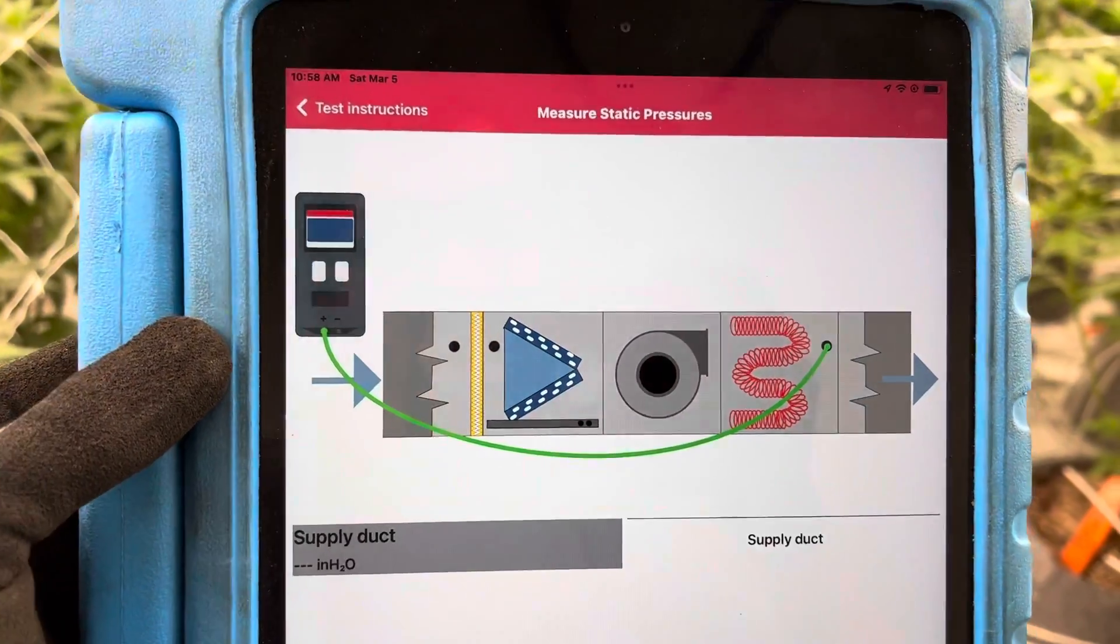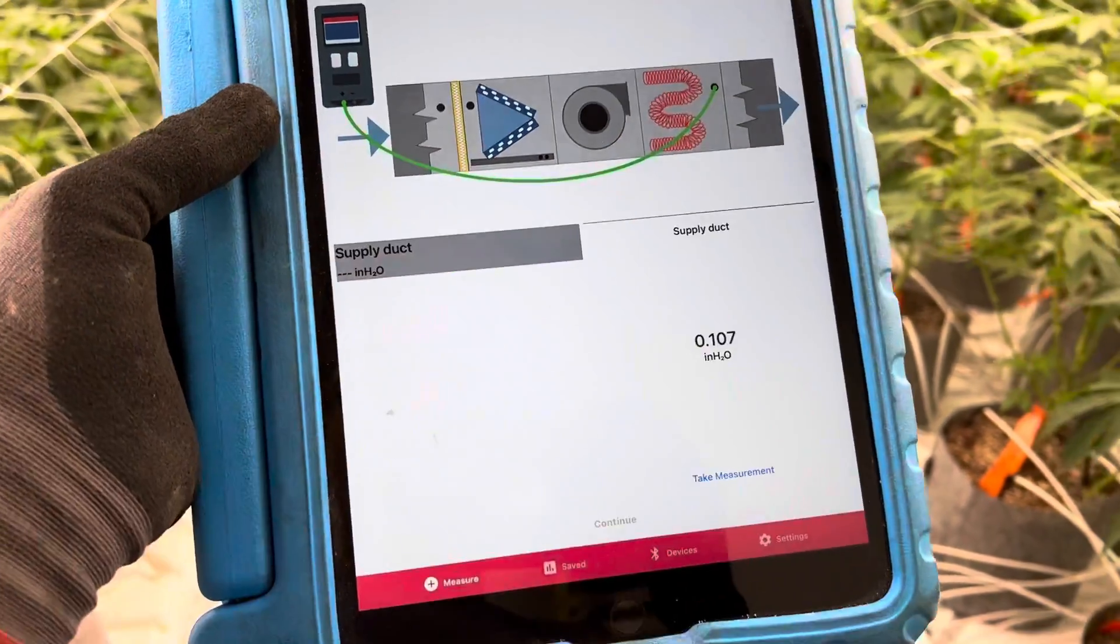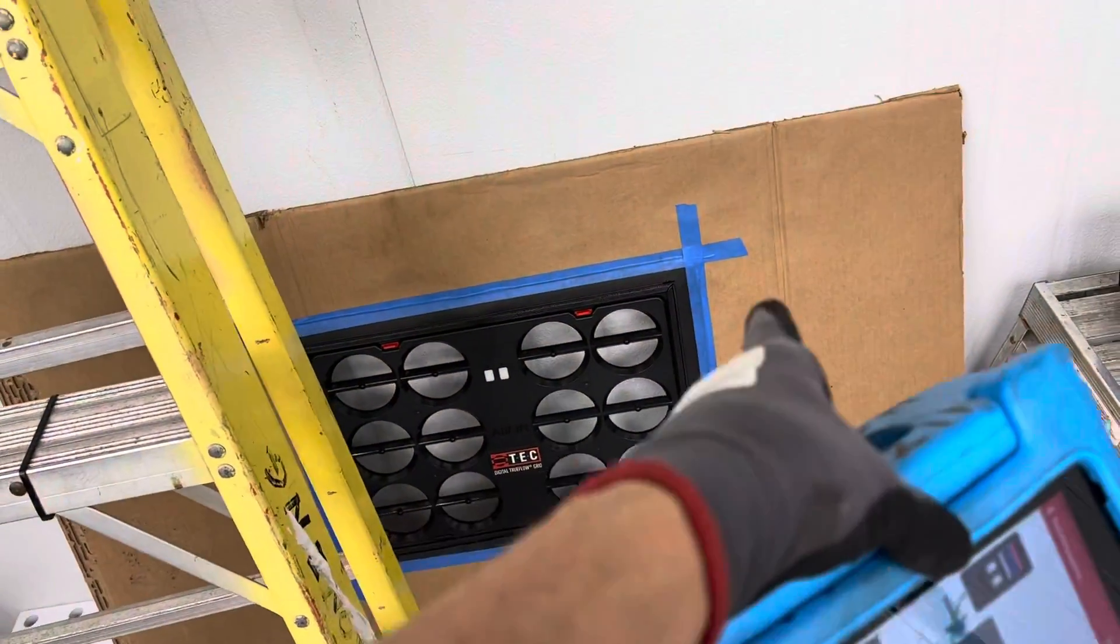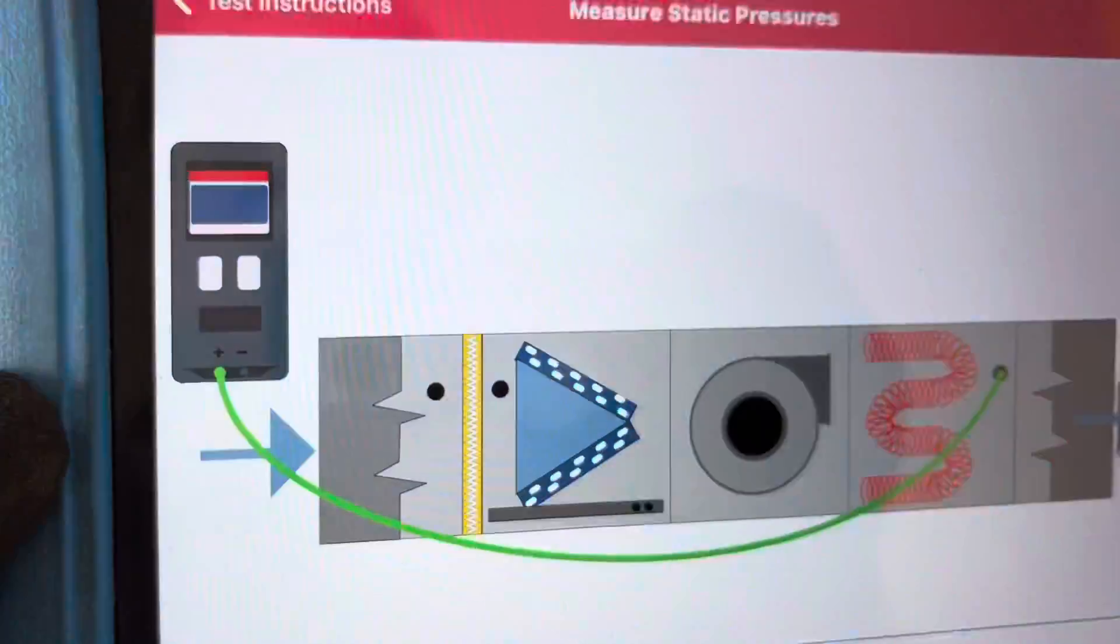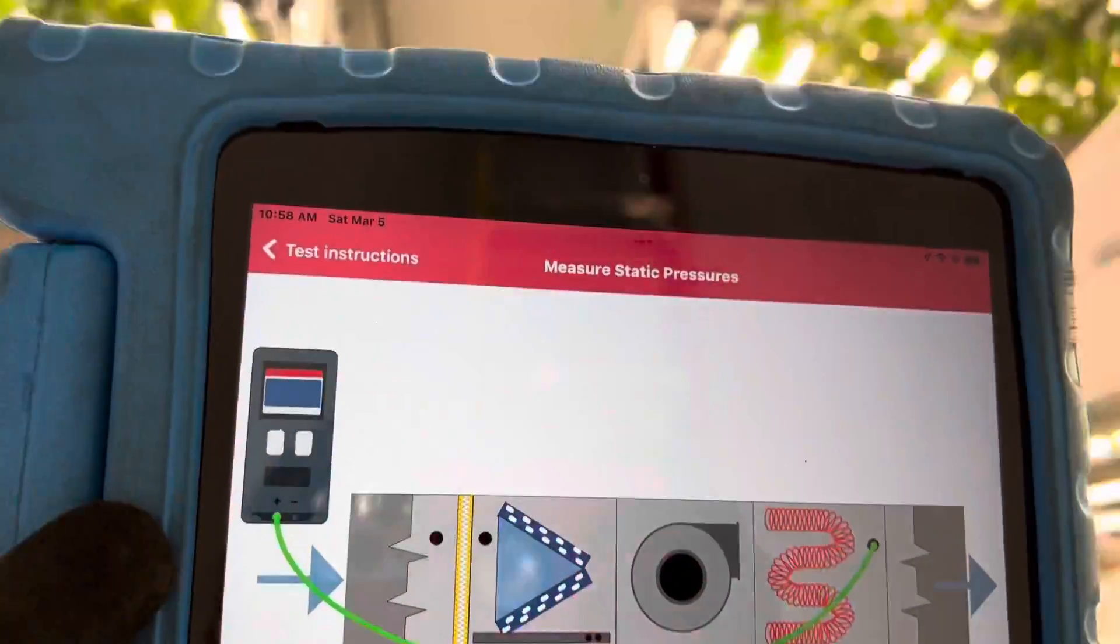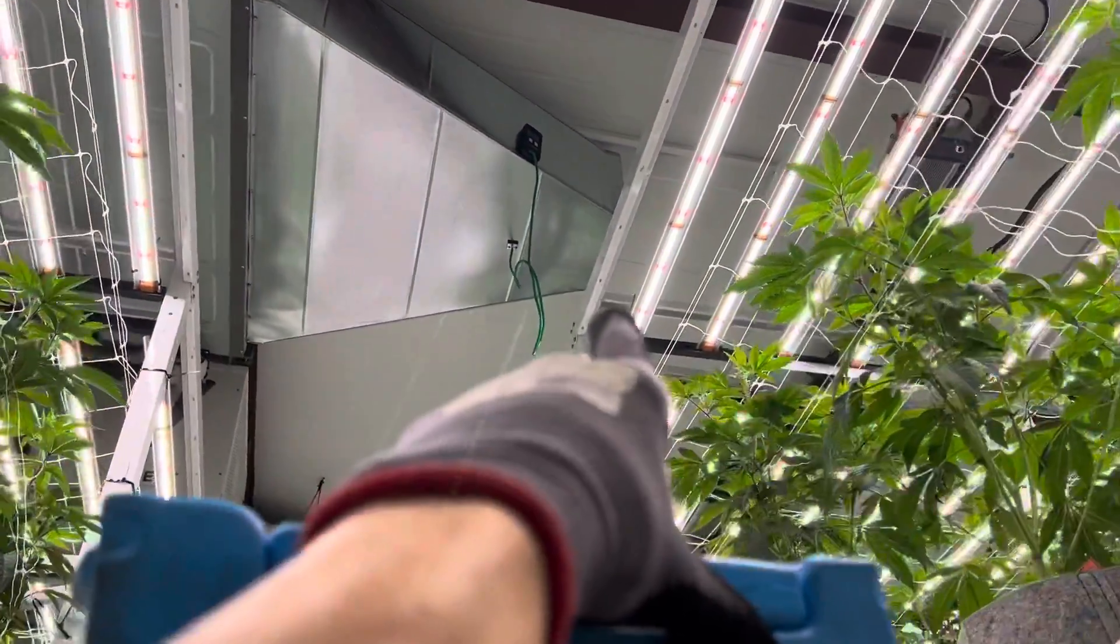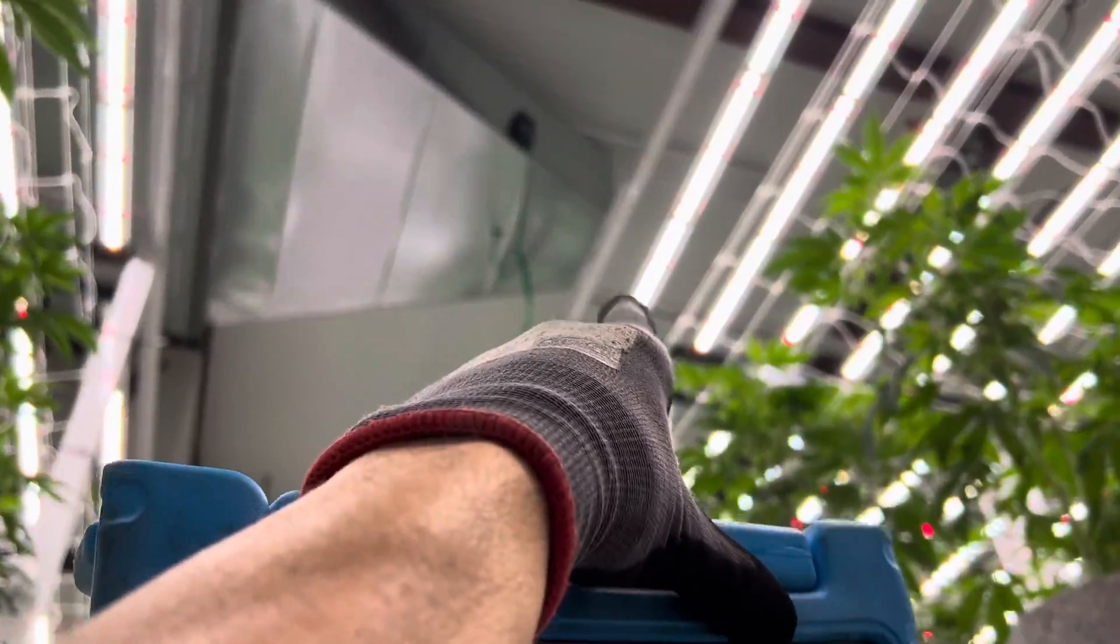All right, about to take a flow measurement using the true flow grid, which you can see right there. I have it in the cardboard adapter to replace the filters, and I just drilled a hole in the ductwork. You can see where the magnet is holding in the hose going in.